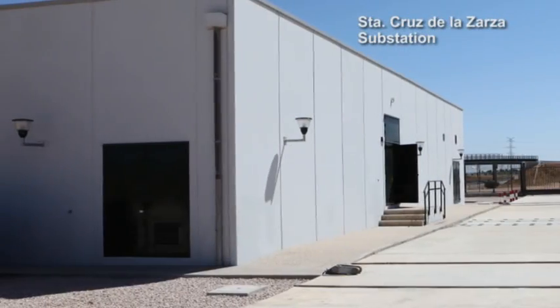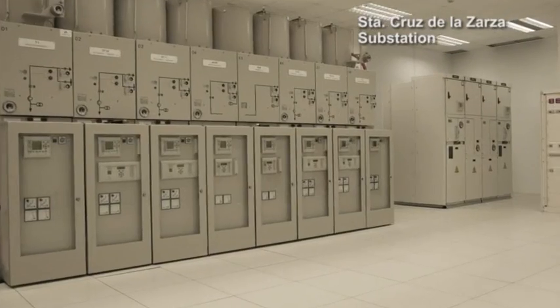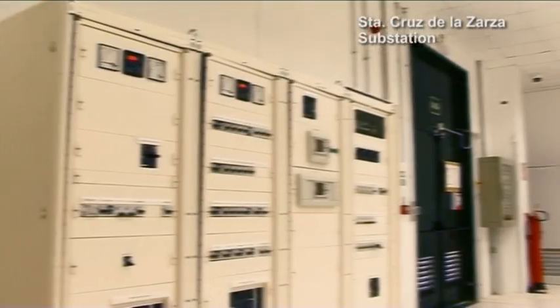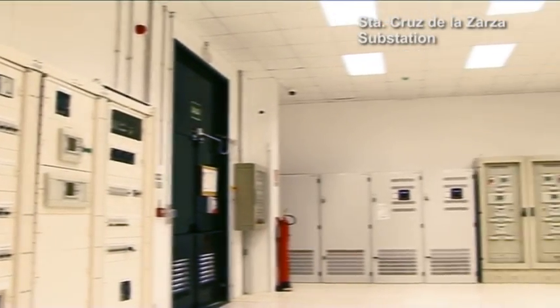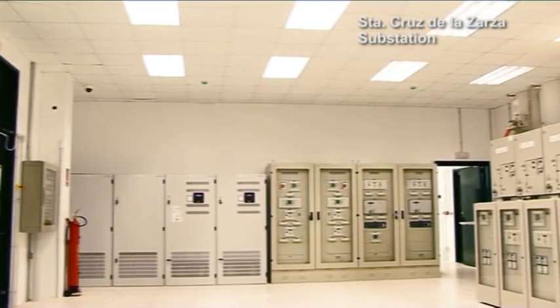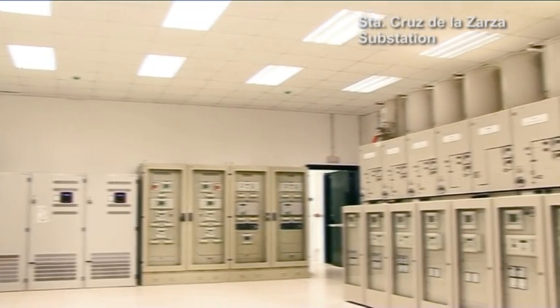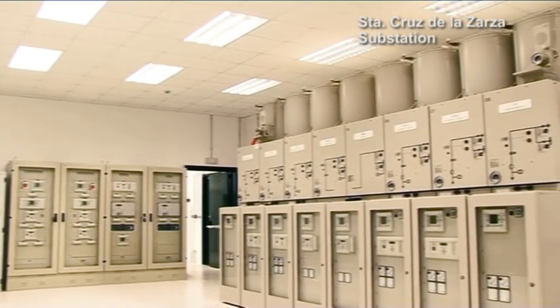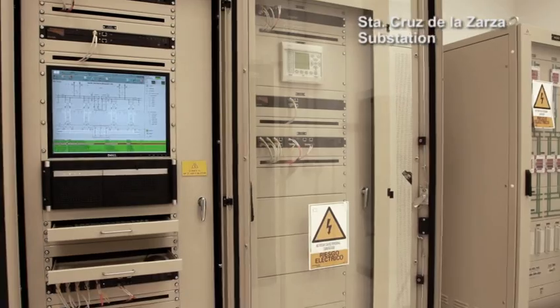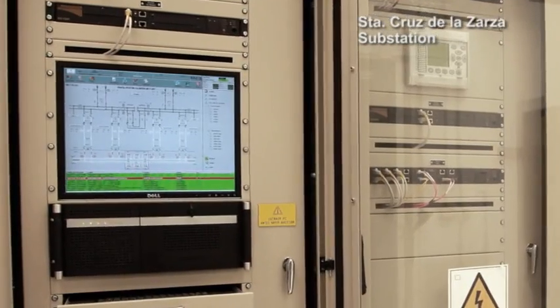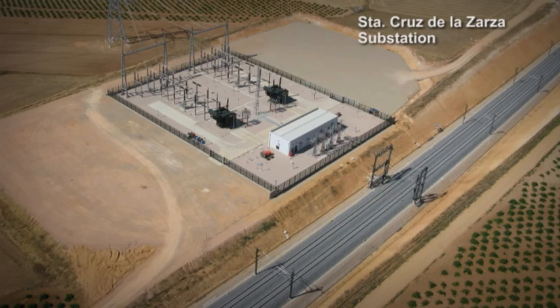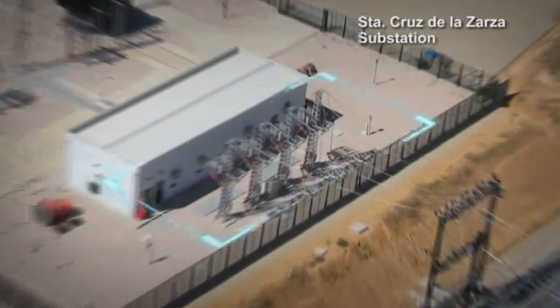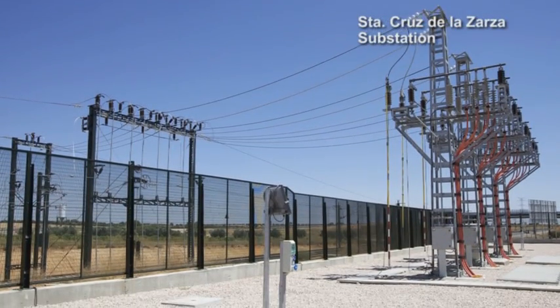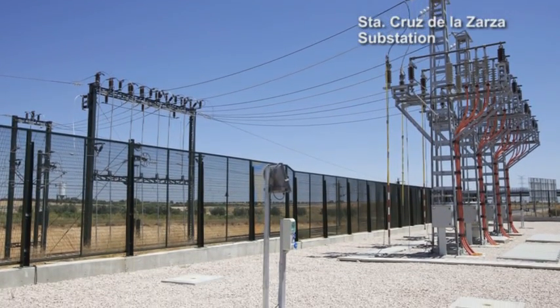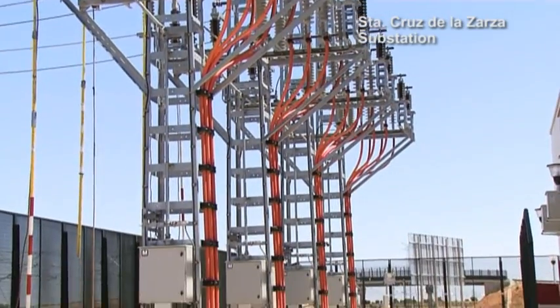The control building contains 2 by 25 kilovolt voltage level equipment plus auxiliary equipment. It's also worth mentioning the modern built-in distributed control and protection system, which allows individual items of equipment to be managed both locally or remotely using energy SCADA. Outside there are overhead contact line output lines, which carry 2 by 25 kilovolts to the train power lines, and the negative feeder typically used in the 2 by 25 system.